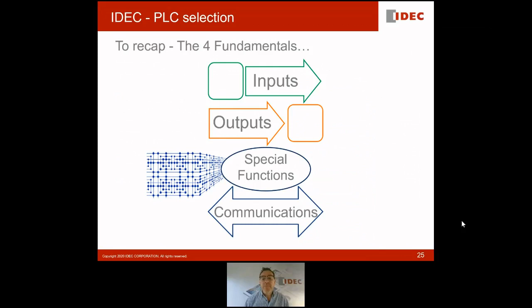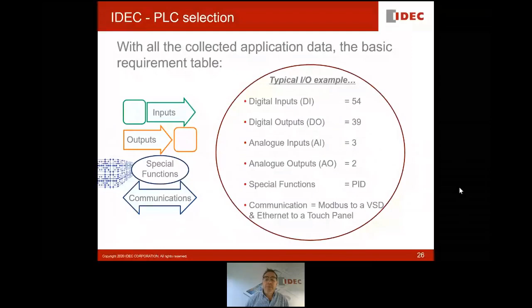So once we've collected all that application data, we've got a basic requirement table. So your DI, your DO, your AI, your AO, your special function and communications comes up with a typical I/O example, as we've got on the right-hand side of the screen there. We've got 54 digital in, 39 out, 3 analog in, 2 analog out. We need PID functions, so we can assume there's some kind of temperature control perhaps going on here. And also we need communications: Modbus to a variable speed drive, and Ethernet to a touch panel. Now we'll come back and revisit this example in a moment, but before we do that, I just want to talk you through some of the hardware that we would look at today for these applications.